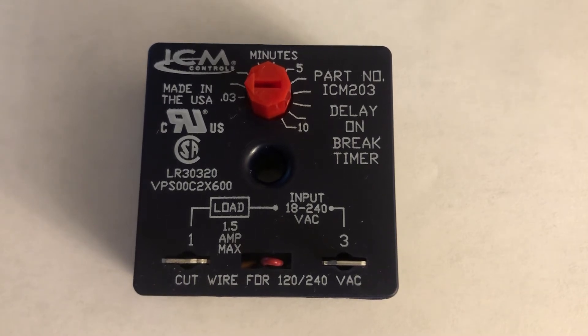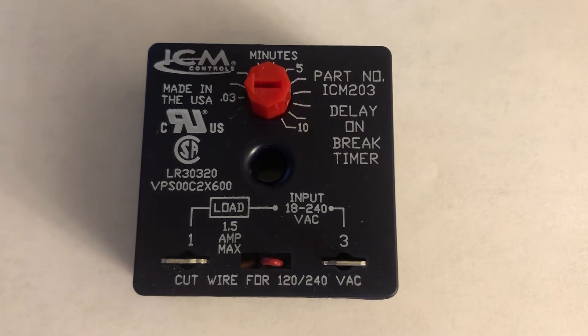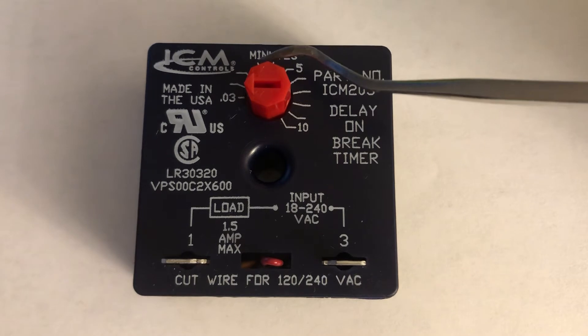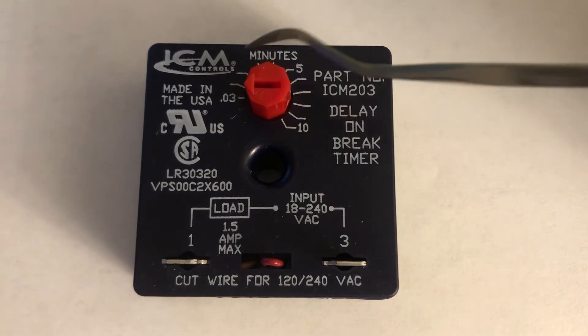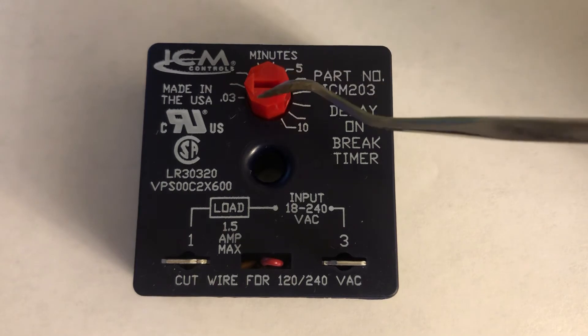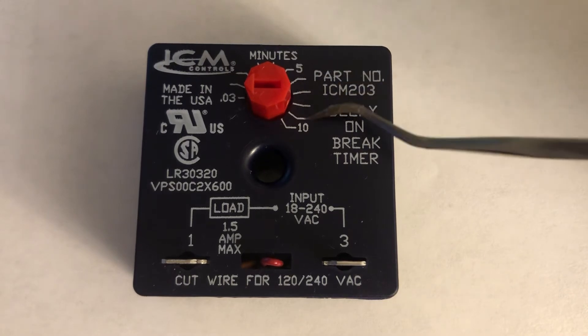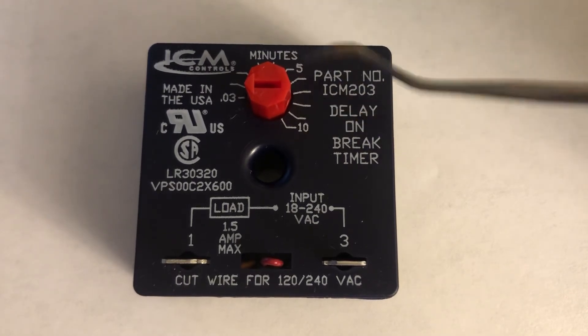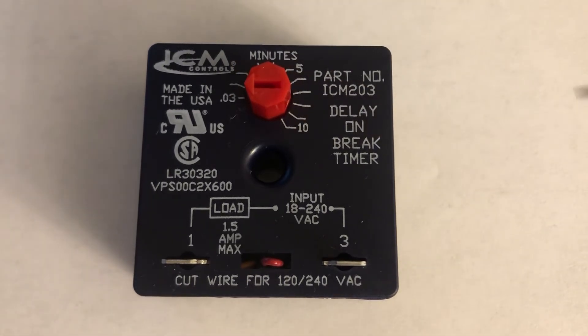This module is a delay timer and it hooks up to your outside AC unit to control your compressor turn-on time. It depends on how many minutes you set it here — the setting can be set from 0.03 minutes to 10 minutes. You manually set it by turning this dial clockwise to however many minutes you want, like 5 minutes, 10 minutes, or 0.3 minutes.